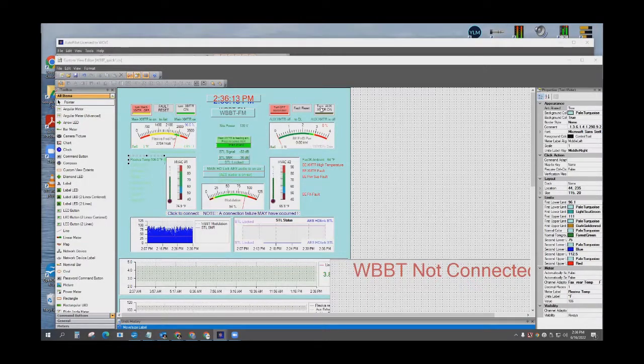For HVAC output, I use one of the simple 4-section Burk metering units. The little boxes are about the size of a wallet with probes, and I put one probe in front of each HVAC unit. This site is small, about 10 by 20, with wall-mounted Bard units, so a couple inches in front of each unit is where I meter the HVAC.